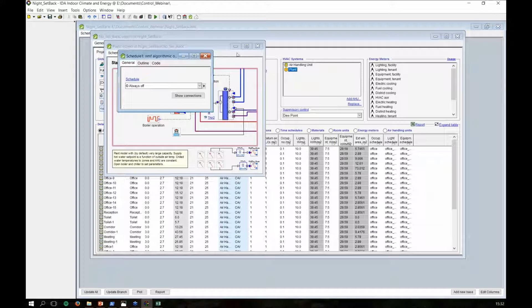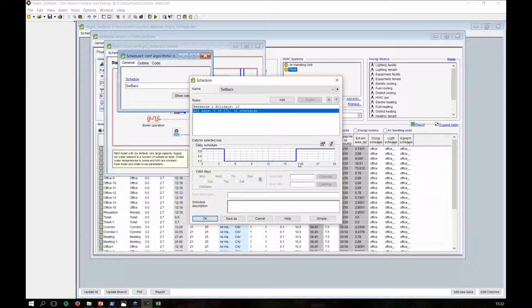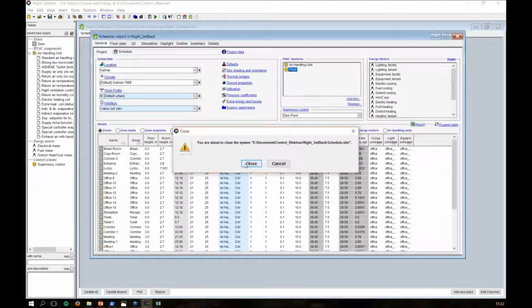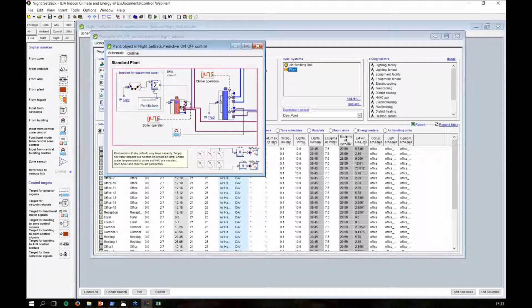For the second case, I'm going to put a schedule, and a typical schedule would be to have setback during normal days between 5 o'clock in the evening and 4 o'clock in the morning, with a setback of 10 degrees, and then no setback throughout the day. And then I'm going to create my own predictive control, which might be a little bit controversial, but I've been tinkering with this for a while now. So instead of a schedule, I'm putting in this macro controller.